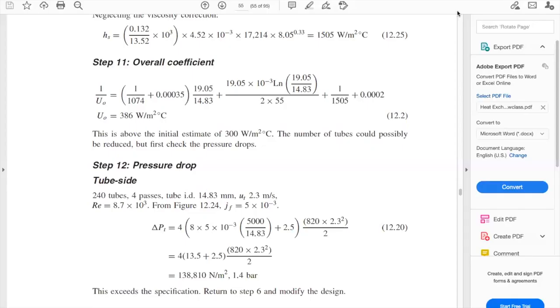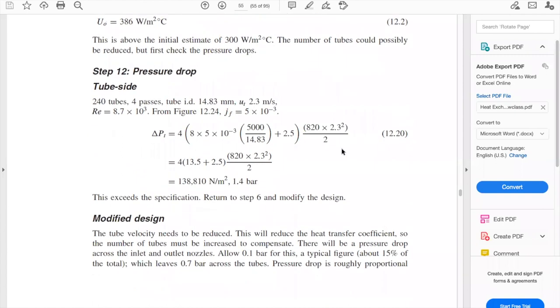We were going through this design problem and talking about the pressure drop. At this point, we have calculated the overall heat transfer coefficient with all the assumptions made in terms of tube size specifications and velocities. We doubled the velocity in the tubes, but we need to check the pressure drop because we cannot just change the velocity without looking at the constraints. That is step 12: check the pressure drop in the tube side first.